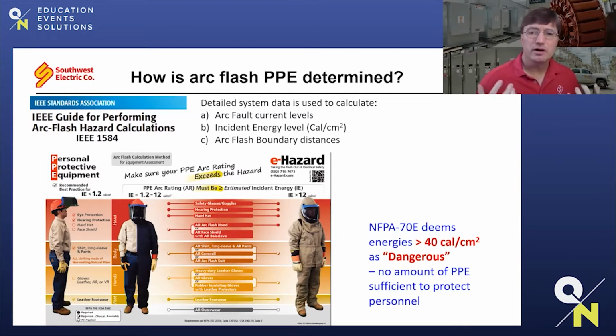So how are these arc flash levels determined, and how do we know what kind of protective equipment we need? Well, the arc incident energy levels are calculated based on a complex set of equations that are developed and governed under IEEE standard 1584. That way, these standards apply to all facilities equally and consistently. Once these equations are determined and the proper protective equipment is determined, this will keep personnel roughly safe based on the energy levels that they're going to be experiencing from various equipment.